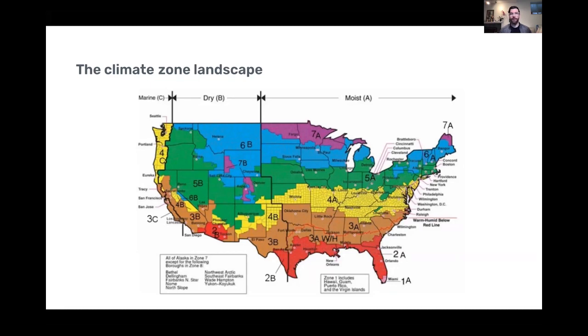Then you can also break it down, and this is where you get into the number side of the climate zone. So anywhere from 1 being the most south and the hottest, all the way up to 7 on this map, which is the coldest region. And so it's broken down by moisture and by temperature. And we like to draw attention specifically to this range of 1 to 4A, where you have a lot of the population in hot, humid environments that can provide a very tricky indoor air quality for these individuals and occupants.